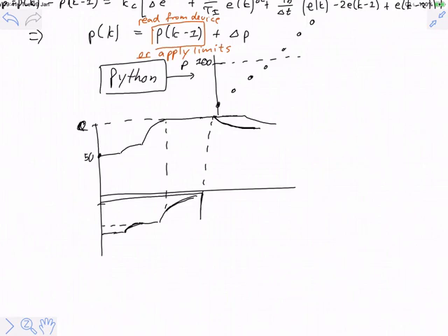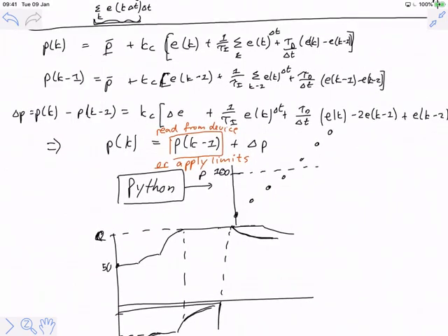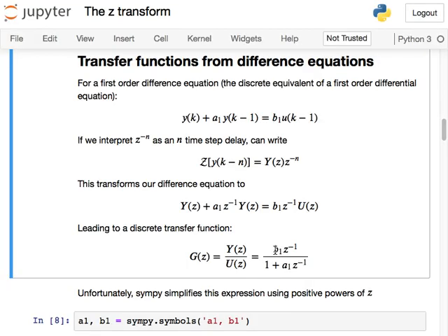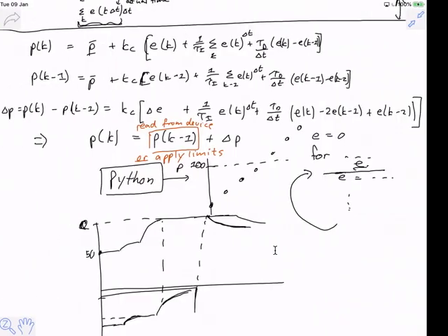They achieve exactly the same results, with the one difference that the velocity form makes it slightly easier, only slightly, not like the position form is impossible, to accommodate read back values of the output. That's the big difference. Really straightforwardly, the last thing I'm going to end this lecture with is I'm just going to show you the Z transform of this.